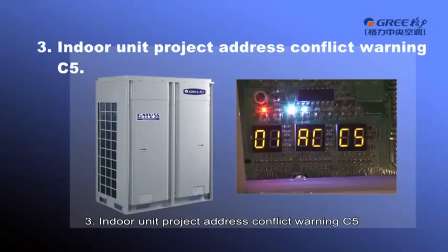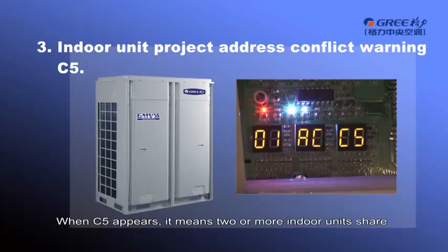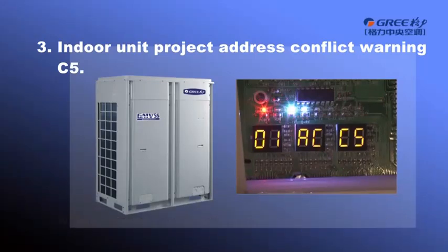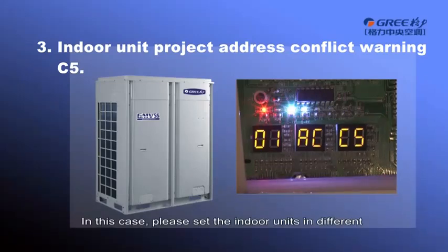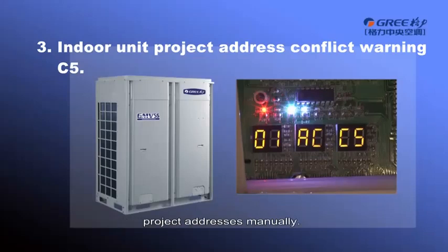Indoor Unit Project Address Conflict Warning: C5. When C5 appears, it means two or more indoor units share the same project address. In this case, please set the indoor units to different project addresses manually.